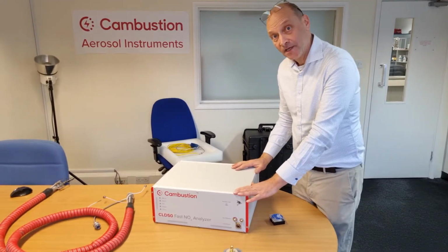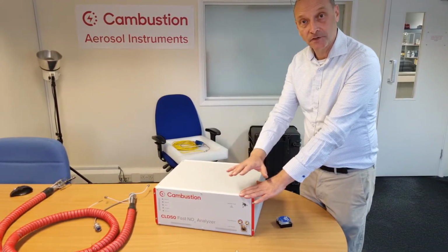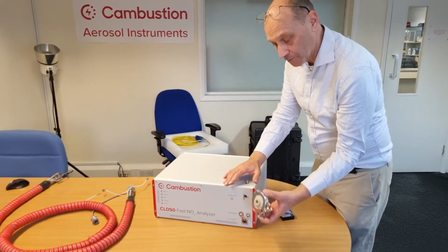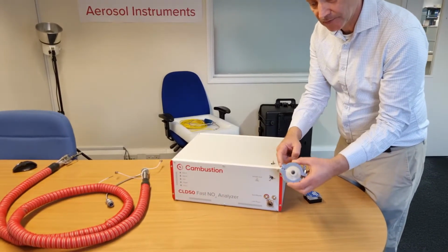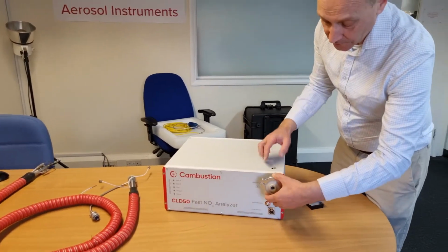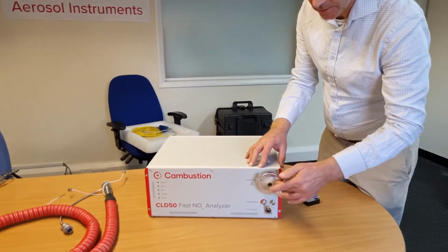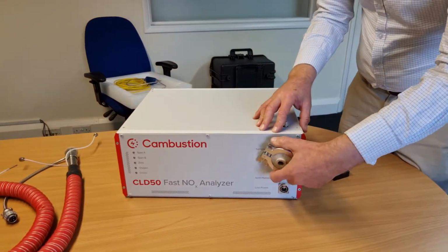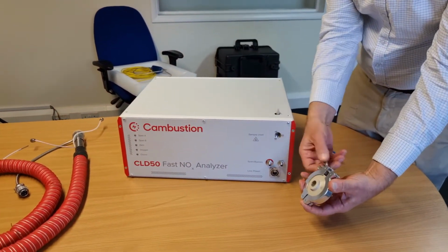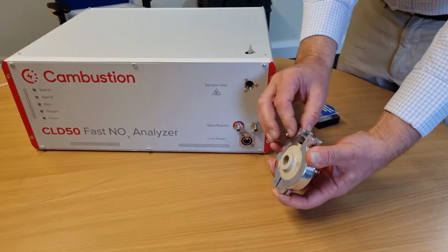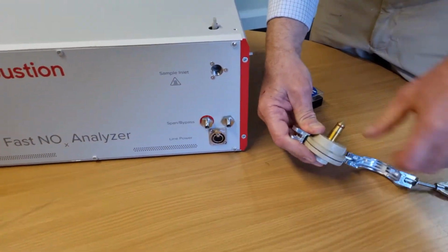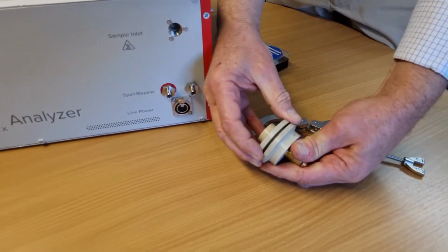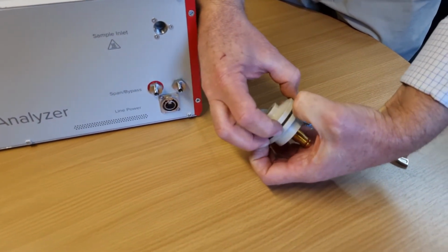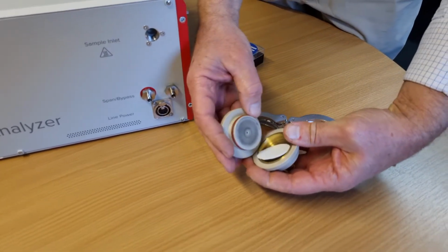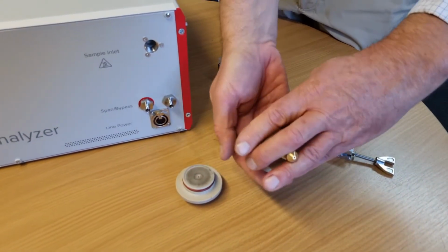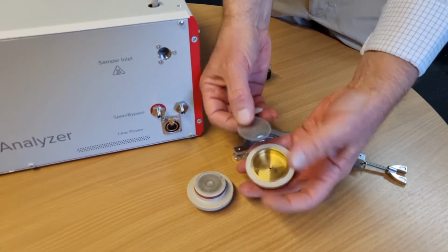What I'll show you now is how to fit the sample line to the front of the analyzer, and what generally goes between the sample line and the analyzer is an inline sample filter. So that screws into the front of the analyzer like that, but I'll show you the contents and the filter paper itself. So you gain access by removing the outer clamp, and then if we separate the 2 halves, there is a paper disc filter inside and a support gauze which holds it up away from the sample hole.